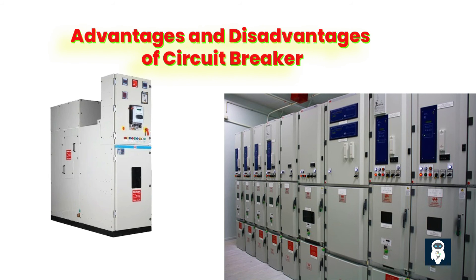Circuit breakers have a rapid response time and accurate fault interruption, making them ideal where immediate disconnection is essential. They are highly reliable and handle sustained or permanent faults more effectively than auto reclosers. However, circuit breakers require manual intervention to restore power after a fault, which can be time-consuming and cause longer outages. They also have a higher initial cost, and their immediate interruption of faults may lead to more frequent power disruptions in areas prone to temporary faults.